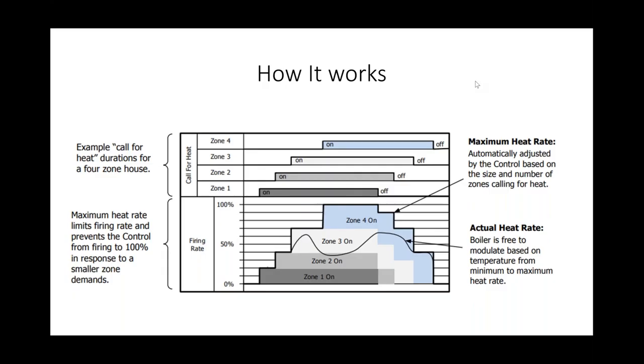A lot of the time it's talked about, okay, we're putting in a 95% boiler, and in real life terms, that boiler is only 90 to 92% when it's seeing return temperatures under 120, 130 degrees. If we're not using outdoor reset and we're letting this thing run to 180 degrees all day long, it's only 88% efficient. It's a very expensive 80% boiler. We'll get some benefits out of the modulation, but not the full benefits of it. So if we really fine tune that system, we can get more system efficiency, not just combustion efficiency.